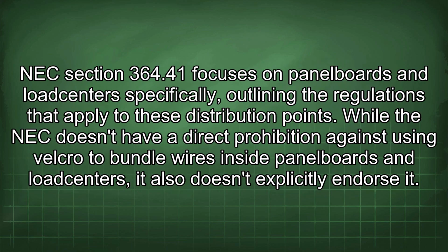NEC Section 364.41 focuses on panelboards and load centers, specifically outlining the regulations that apply to these distribution points. While the NEC doesn't have a direct prohibition against using Velcro to bundle wires inside panelboards and load centers, it also doesn't explicitly endorse it.